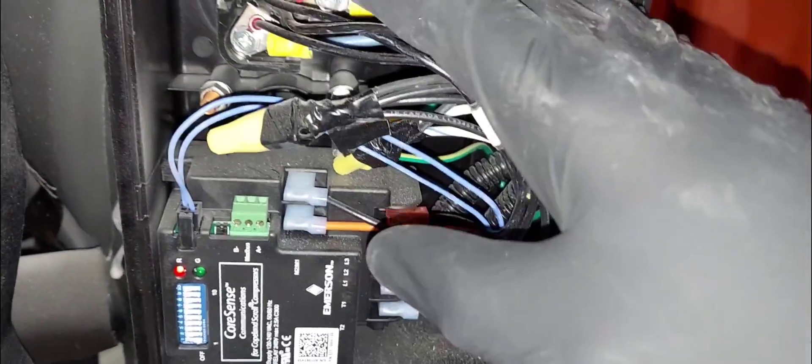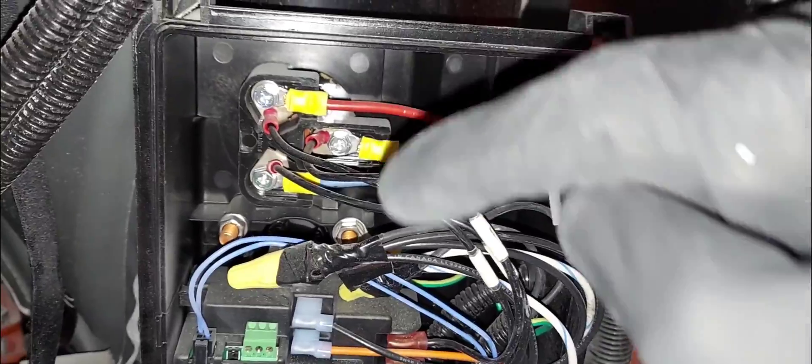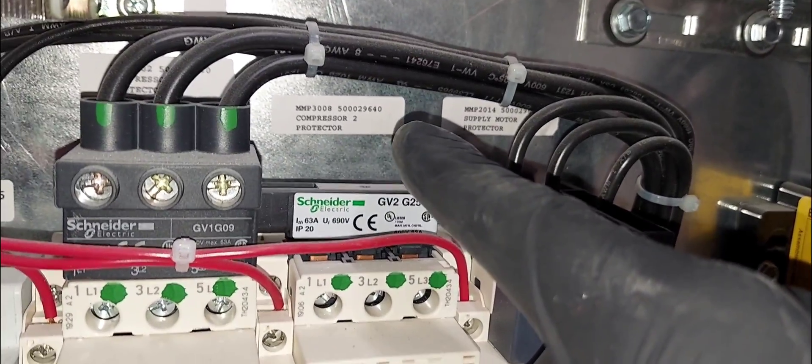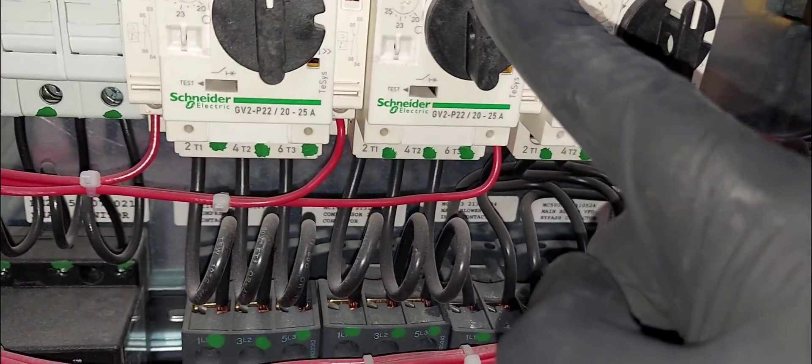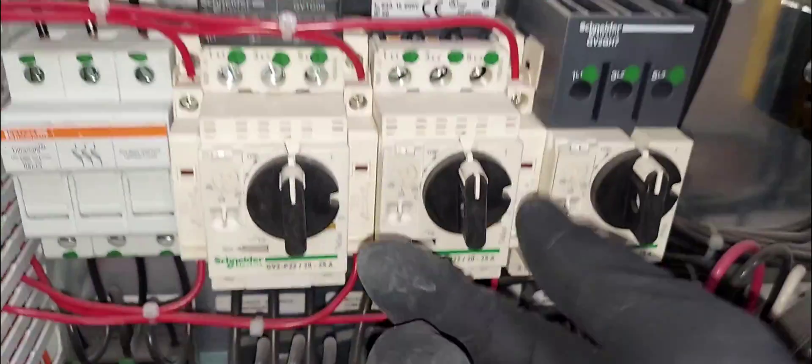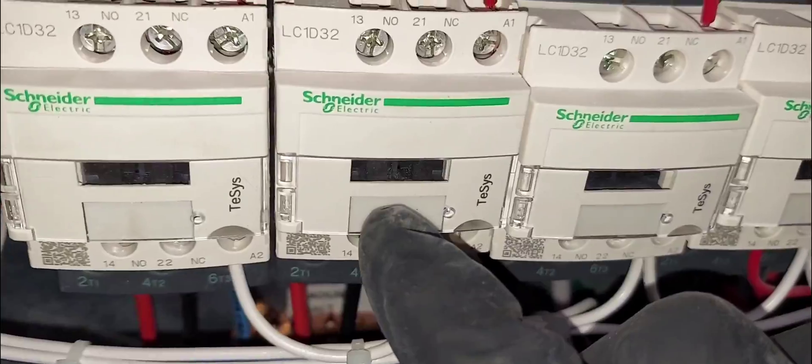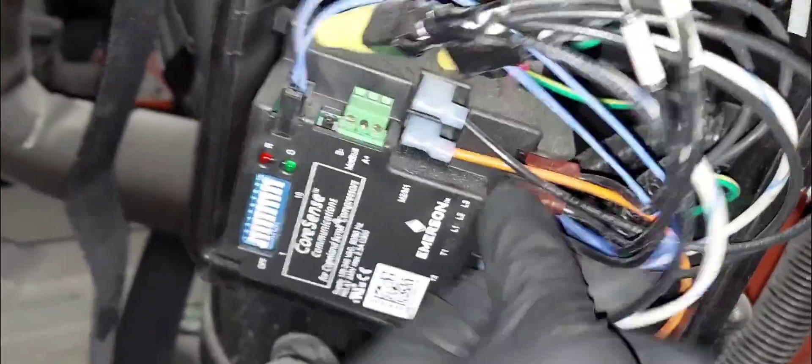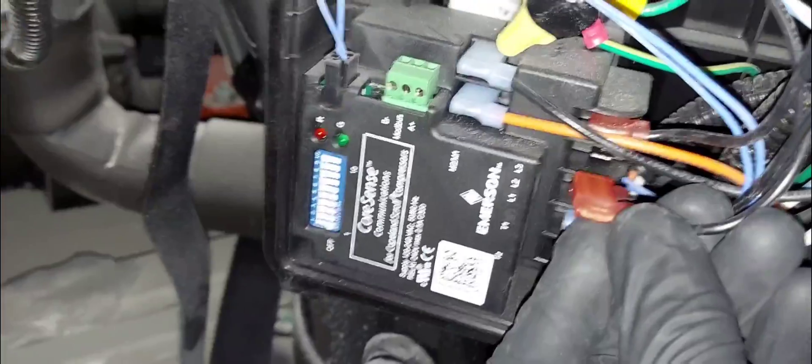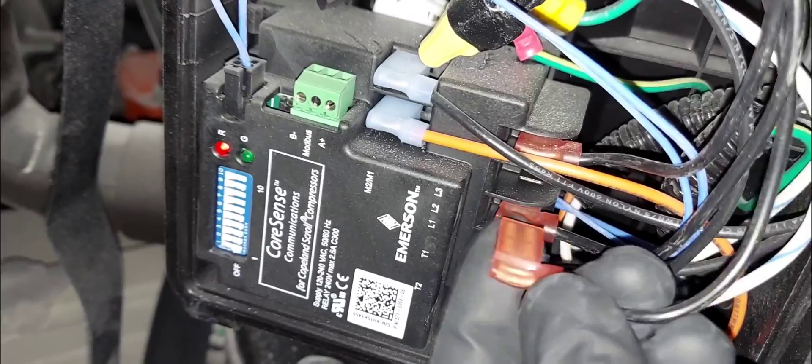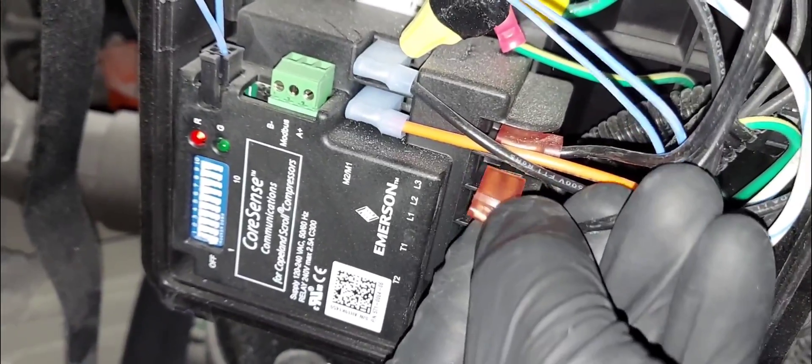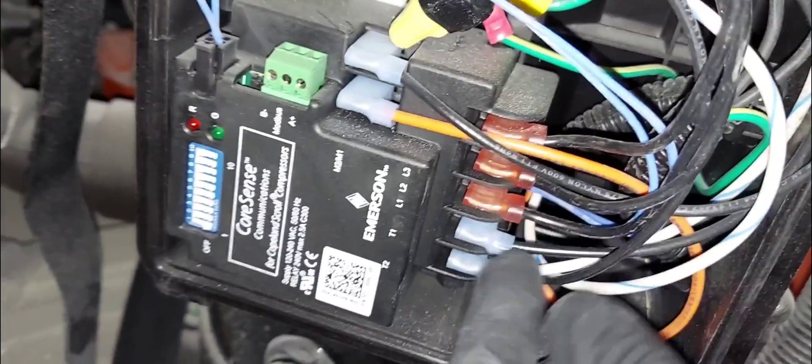To solve that, all I'm going to do is simply pull that. There's no power right here now - this is dead because this is going to turn on when the compressor contactor energizes. The compressor contactor which is compressor number two right here - here's the starter and here's the contactor overload which is a part combined as a starter. Just to be safe I'm going to shut that off. The contactor is currently being energized, so I'm going there real quick and I'm simply going to just switch just two of these phases right here. I just switched two of these phases. I switched these two. I think it should be correct now.